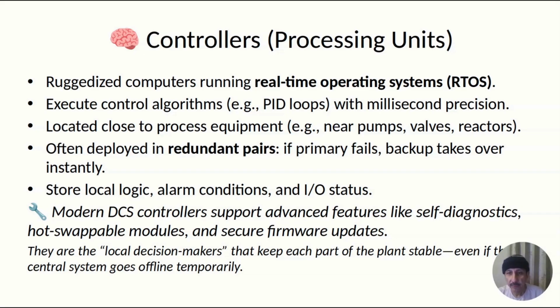Most modern DCS controllers also support redundancy. Two identical units will be run in parallel, one active, one standby. If the primary fails, the backup takes over so fast that the process doesn't even notice. And yes, they can be updated remotely, diagnosed online, and even predict their own failures using embedded health monitoring.